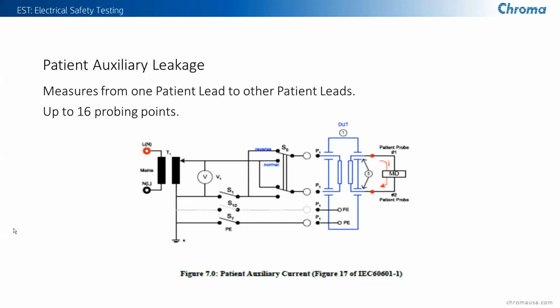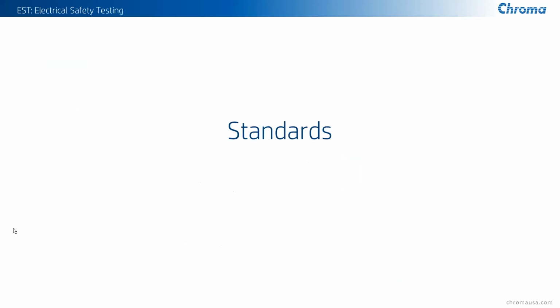Patient auxiliary leakage is from one patient lead to another. For example, if you were in close proximity to another patient while you were attached to a piece of medical equipment, that would give you the ability to make contact, and if there was that point-to-point contact, there may be a possibility of leakage current flowing through that could cause some kind of hazard.